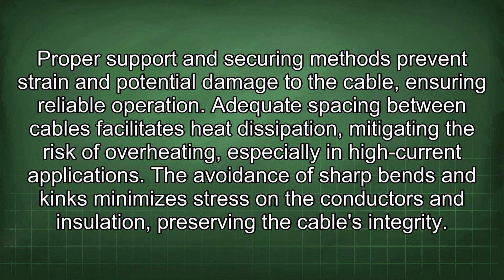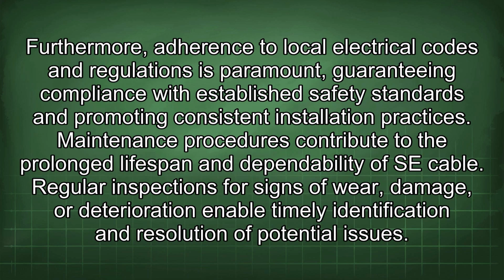Proper support and securing methods prevent strain and potential damage to the cable, ensuring reliable operation. Adequate spacing between cables facilitates heat dissipation, mitigating the risk of overheating, especially in high-current applications. The avoidance of sharp bends and kinks minimizes stress on the conductors and insulation, preserving the cable's integrity.